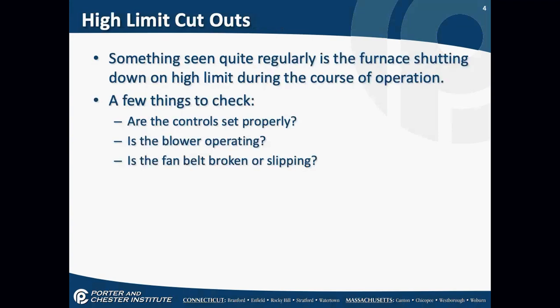Something seen quite regularly is the furnace shutting down on high limit during the normal course of operation. In other words, you're going to be in the basement. You're going to see the furnace run quite normally. The fan continues to run, but the burner shuts off. The fan continues to run. Then the burner comes back on after a few minutes, shuts off again, and it cycles.